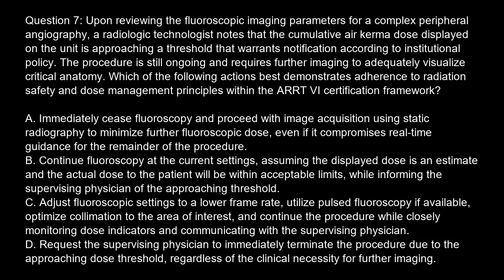Option C. Adjust fluoroscopic settings to a lower frame rate. Utilize pulsed fluoroscopy if available, optimize collimation to the area of interest, and continue the procedure while closely monitoring dose indicators and communicating with the supervising physician. Option D. Request the supervising physician to immediately terminate the procedure due to the approaching dose threshold, regardless of the clinical necessity for further imaging.